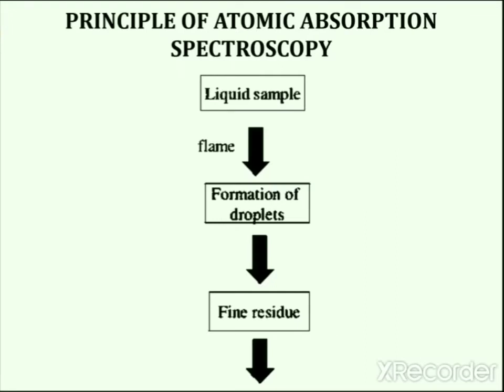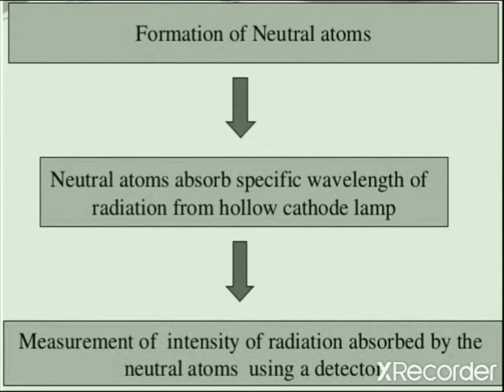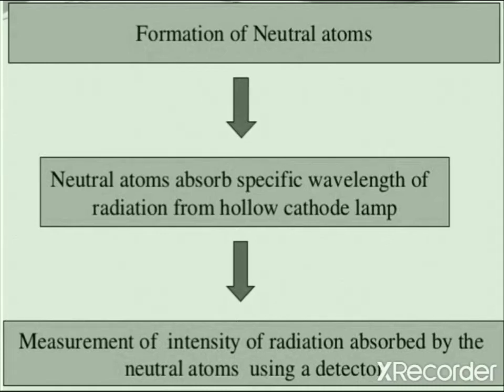In Atomic Absorption Spectroscopy, when a liquid sample is introduced in a flame, it is vaporized leaving a solid sample residue. The solid sample residue is then converted to an atomic state. Radiation from a specific light source is focused on the atomic vapor in the flame. The light radiation enters a monochromator which isolates the line of interest, is measured by a photomultiplier tube, and the signal is processed and the computer system prints the output on screen.